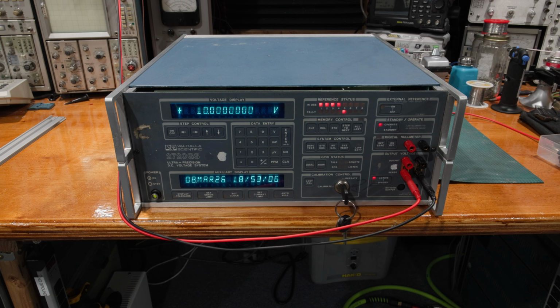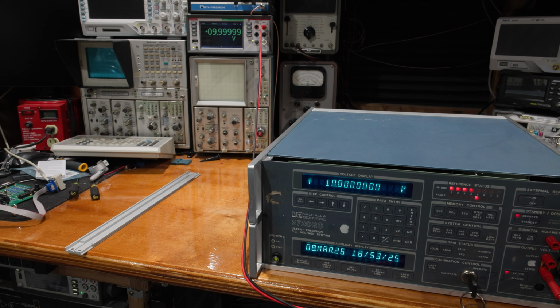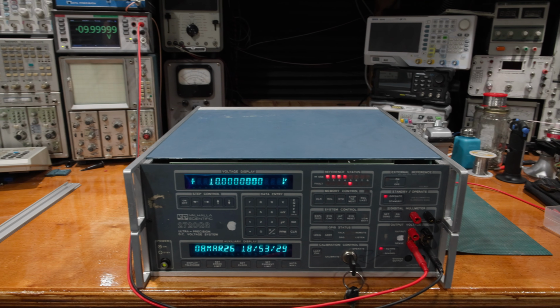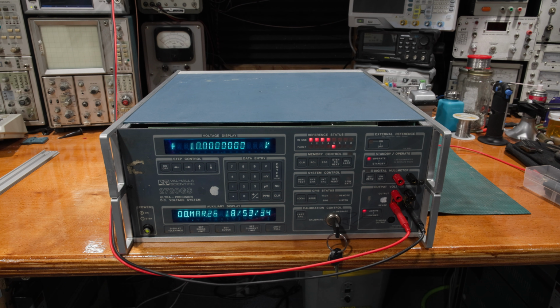Something was bothering me as I was getting this video prepped and edited and ready for the editor for YouTube. I should not have been that far off after just calibrating it, because the 5440B is a known good supply. And no, we should not have been. So when I did the system check and told it to repair the calibration data, it got bad calibration data back in. So we've got to pull that 22221 module out of the unit, and I have a sneaking suspicion that memory module is having some trouble. So let me get that pulled out, and then we'll see if it'll do another calibration and warm up, because it's erroring trying to write the constants to that IC. It's the only thing I can think of at the moment that would explain that.